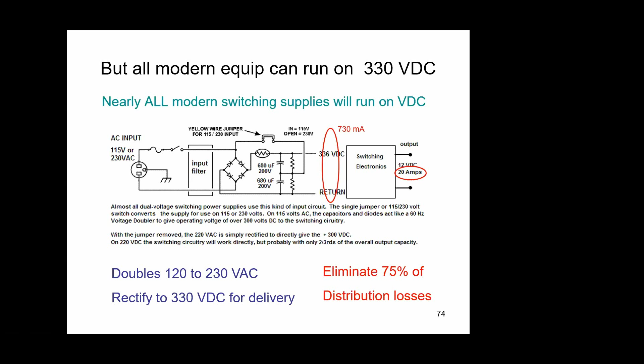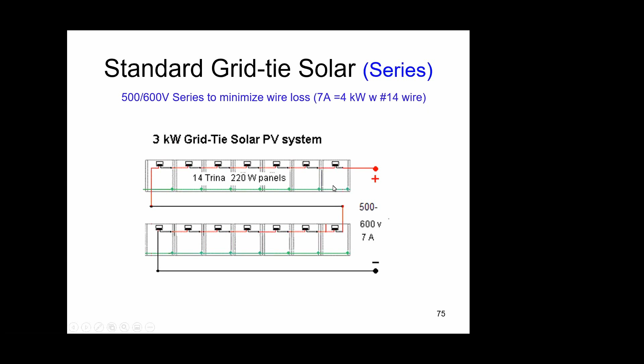Now let me make a short diversion, because I wanted to tie this all into the fact that everything is high voltage DC. What's ideal, instead of wiring all your panels in series up to say 450 to 500 volts, is to put a tap in the middle so you can arrange those panels during grid down conditions into 2 arrays in parallel. Now you've got 15 amps at 300 volts. And almost everything with universal power supplies now can run on that kind of DC.